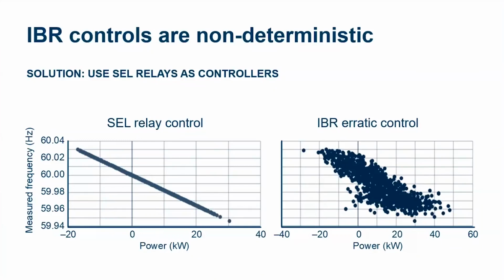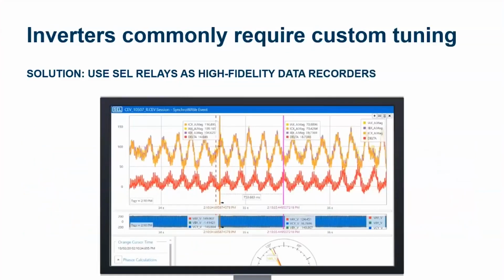Inverter-based resources are especially non-deterministic for the many reasons I've mentioned. Here's an example of erratic control on a droop line from an inverter-based resource. Turn that off. Let a relay do the job. Relays are extremely good droop controllers. And so this is the result you get when you replace an inverter control package with mystery meat software with an SEL relay that you programmed.